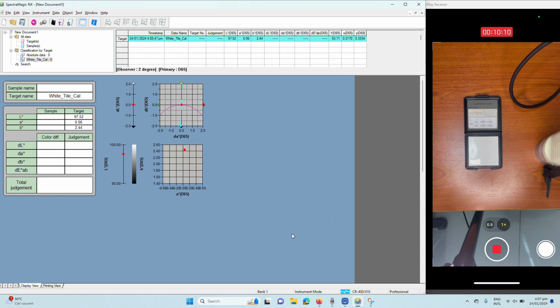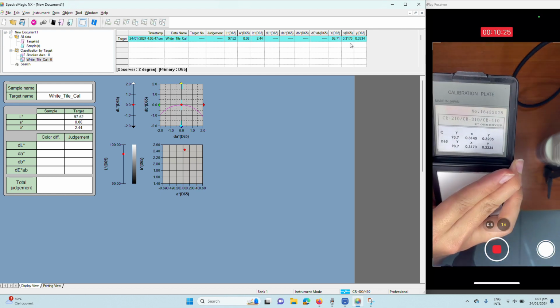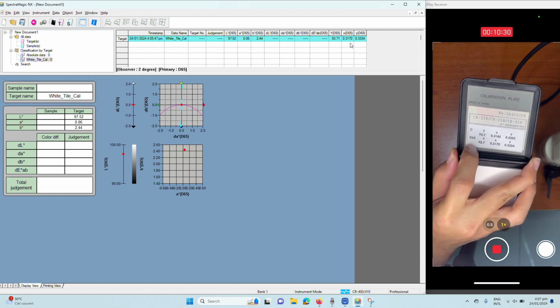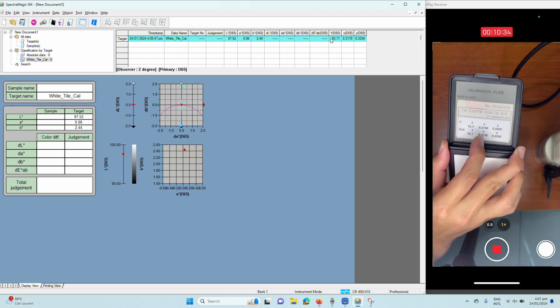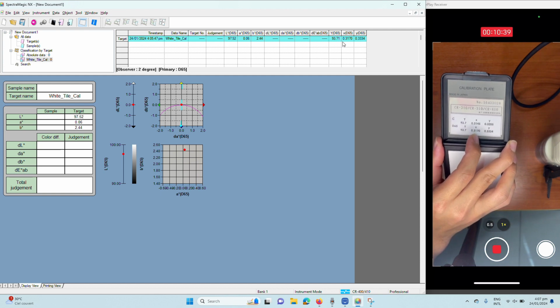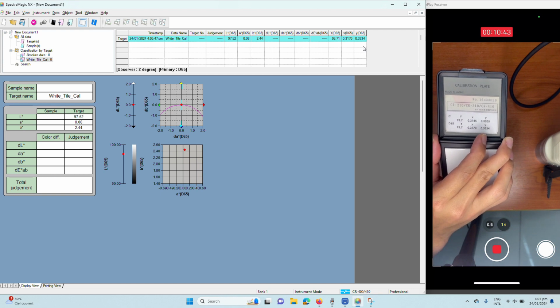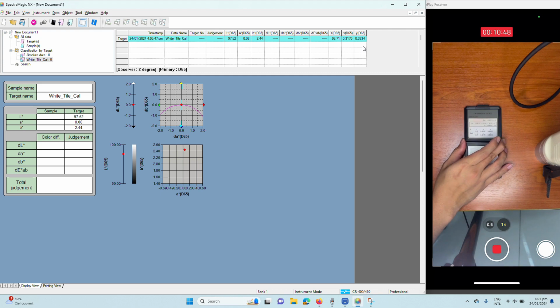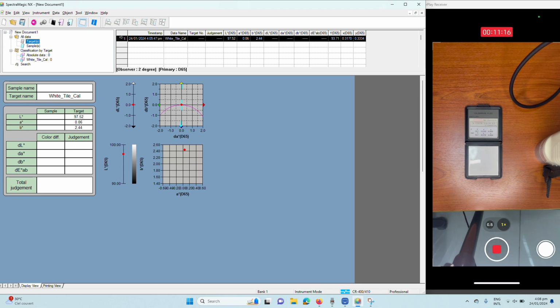There we go. So this is the current settings, and you can see from here, let's check if the value is very, very close. So of course you got, first of all, Y equal to 93.7, very close to what we have, and then X is 0.317. Then another one, for small y, is 0.3334. That means that your equipment is rightly calibrated. And if it's very different, very far away from the value of the white plate, you might have to consider sending your equipment to the authorized service technicians. So here you go. This is the setup of the calibration. So let me delete this so it doesn't interrupt our measurements.